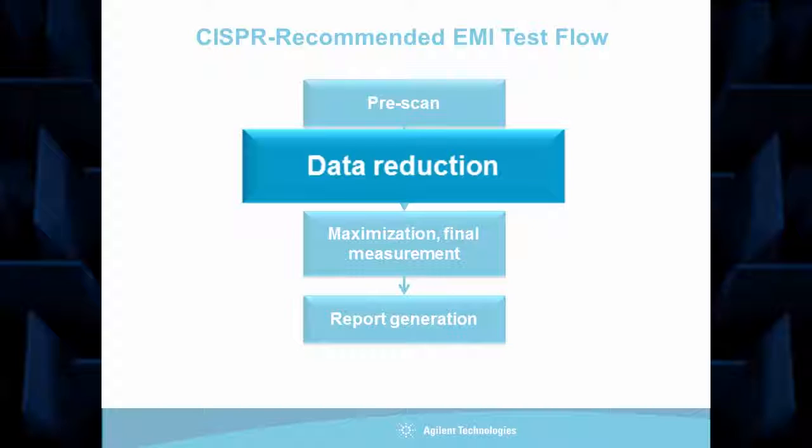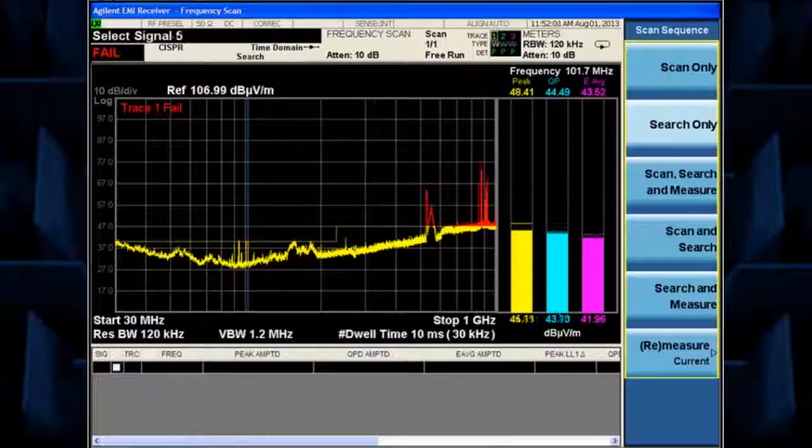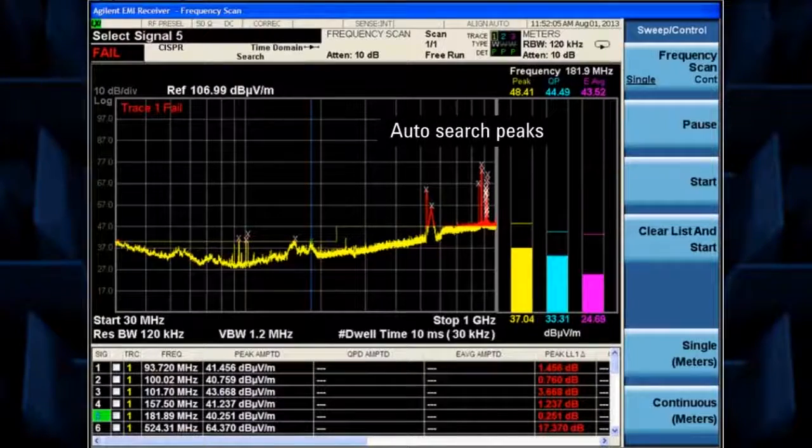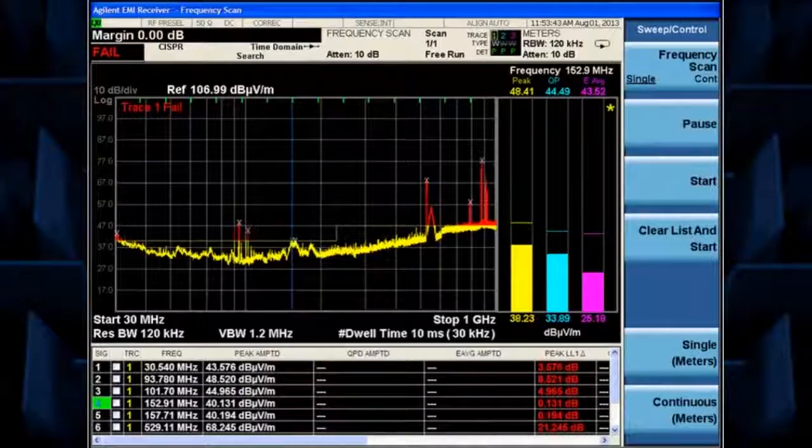Next, let's do data reduction. The MXE will automatically search for any signals exceeding the limit and populate the signal list. MXE can also search in sub-ranges. Quickly mark and delete signals in the signal list.